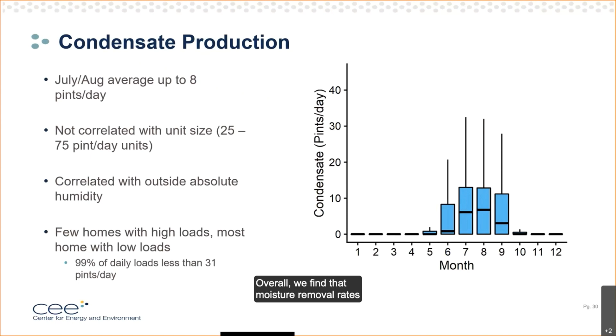Overall, we find that moisture removal rates are not correlated with unit size. So we had units in the study from 25 to 75 pints, and the moisture removal rates were not correlated at all with their size. We found they were highly correlated with outdoor humidity, which is not really surprising. But overall, we found that moisture loads on about 80% of the homes are very low. And over 99% of days in this study, that's less than 60 out of almost 7,000, are less than 31 pints per day, or about the smallest rated size of unit on the market.